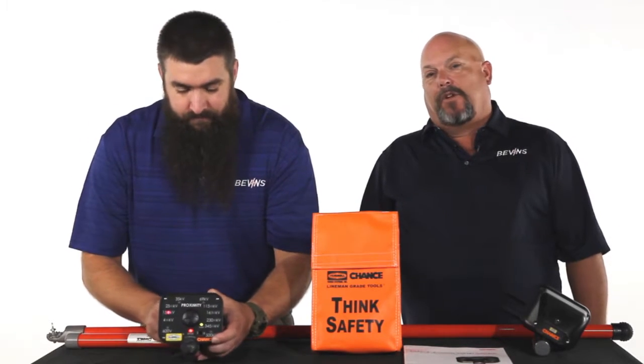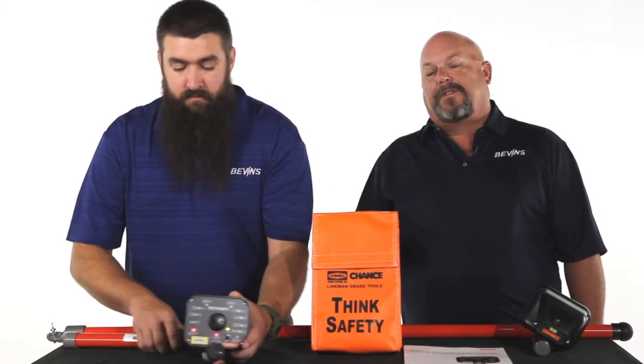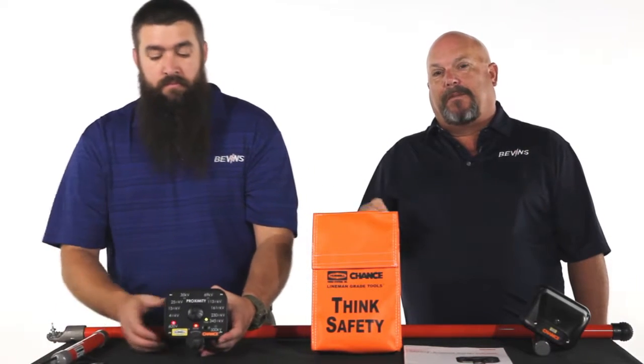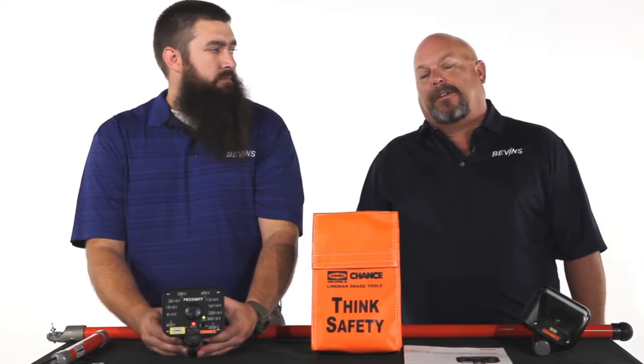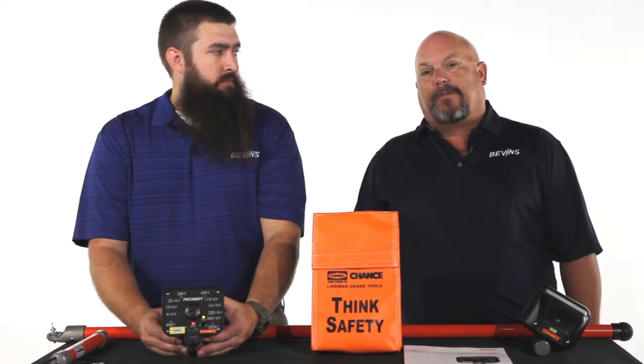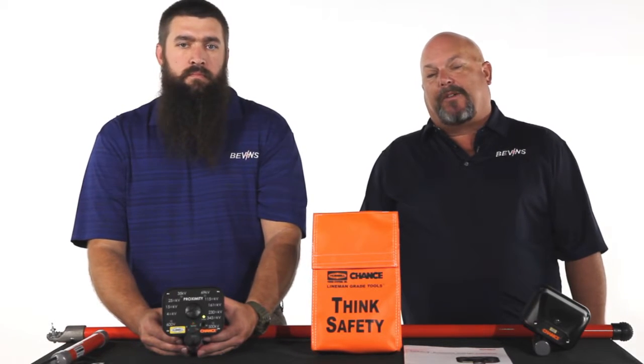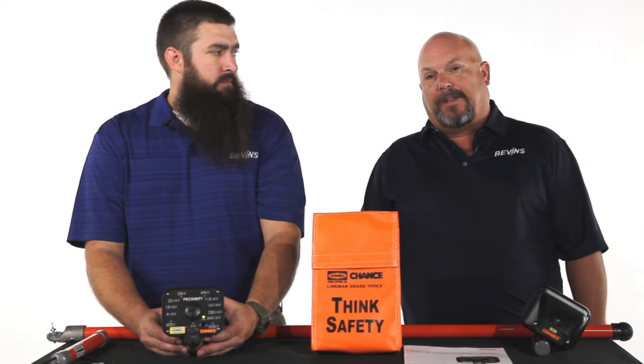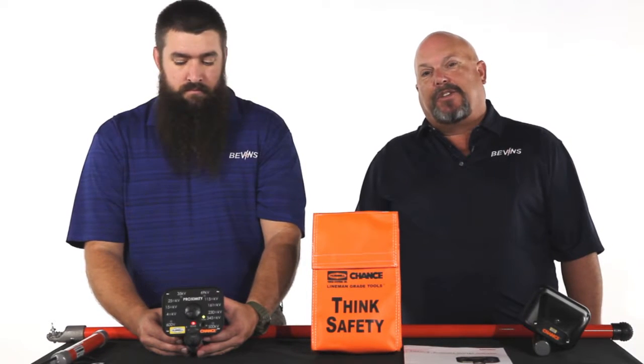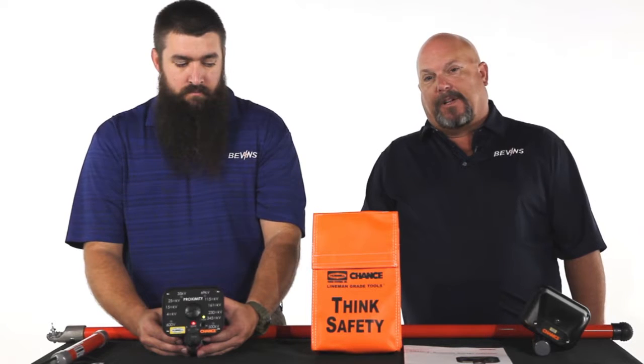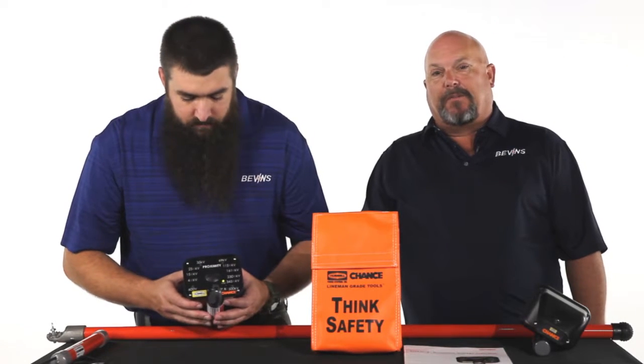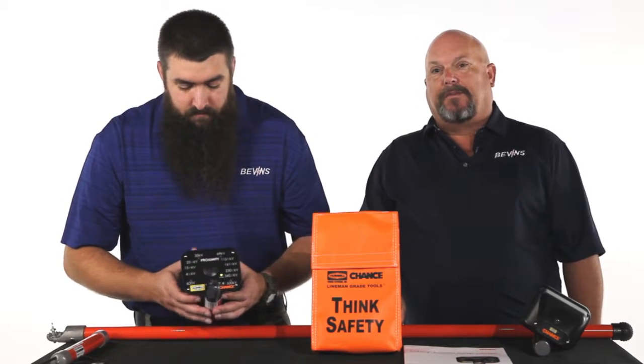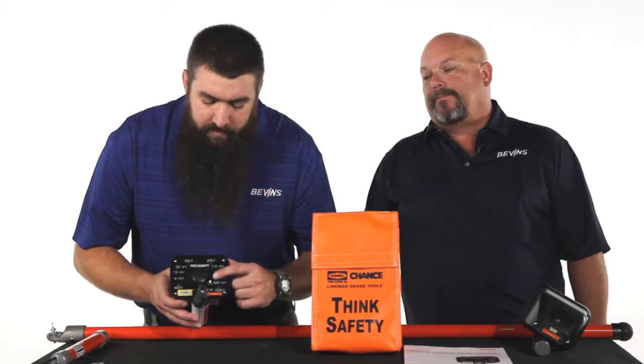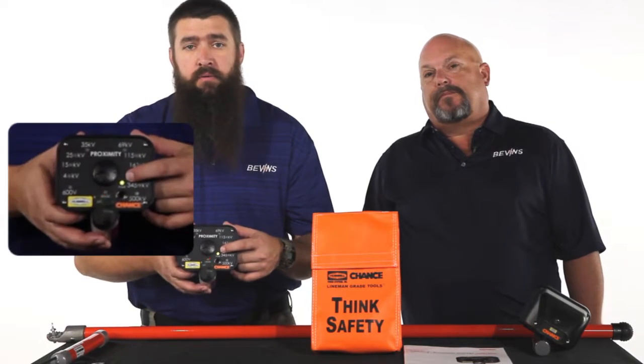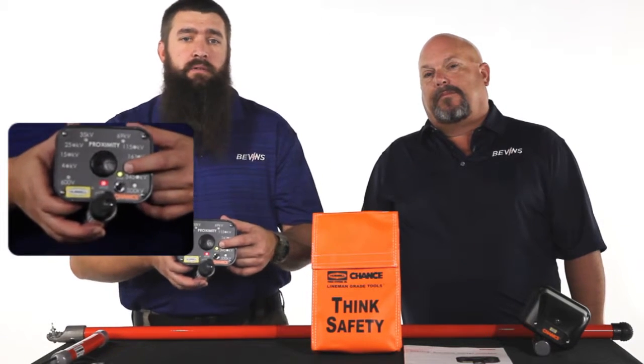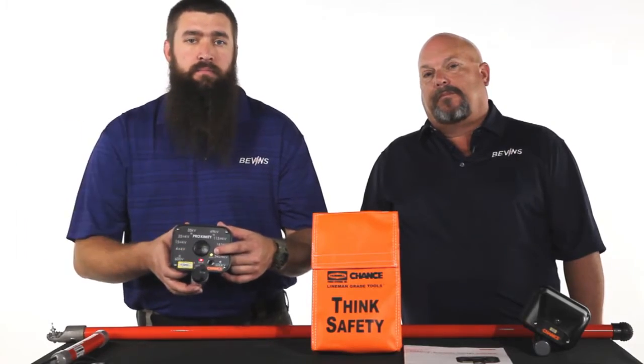And if you see a low reading, that could mean two things. First of all, the tester battery, which again is a 9-volt battery, could be low, or the batteries in the unit, which are AAs, could be low. So there are two things that could be going on if you do see a low reading. You should check your batteries. Our power LED, this green one here, will begin to flash on the proximity unit if the batteries are getting low.